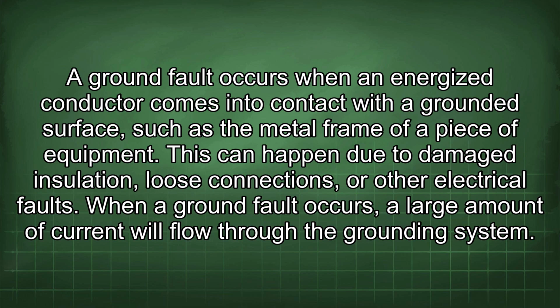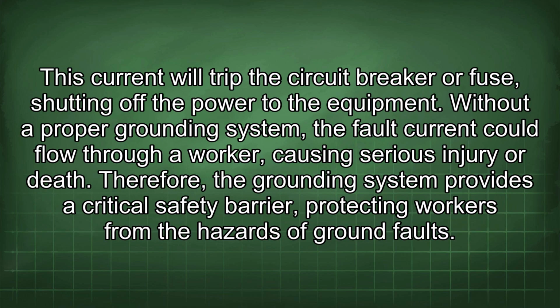When a ground fault occurs, a large amount of current will flow through the grounding system. This current will trip the circuit breaker or fuse, shutting off the power to the equipment. Without a proper grounding system, the fault current could flow through a worker, causing serious injury or death. Therefore, the grounding system provides a critical safety barrier, protecting workers from the hazards of ground faults.